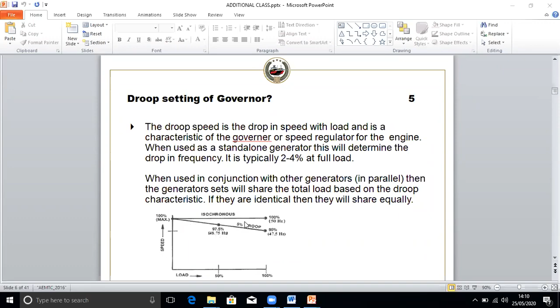Here there's a question: can you parallel an emergency generator with an auxiliary generator? You see, the one which has less droop will take more share of the load. Let's say you have a large generator and a small generator, or an emergency generator and an auxiliary generator. For running in parallel, the voltage, frequency and phase angle should all be the same, irrespective of the kilowatt rating. Technically there is no restriction in running an emergency generator and auxiliary generators in parallel, and some ships have this provision of paralleling an emergency generator with an auxiliary generator.